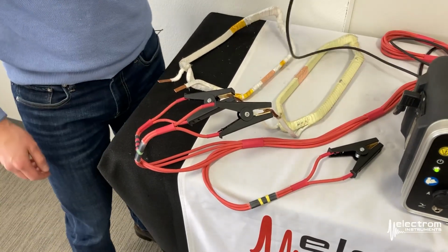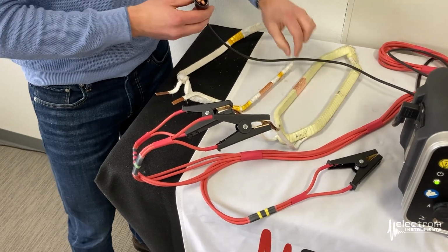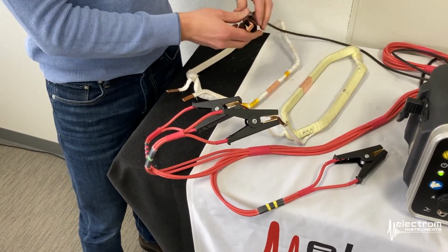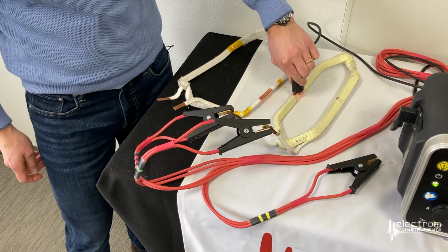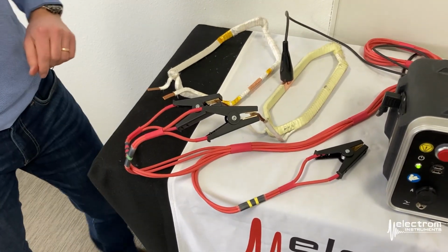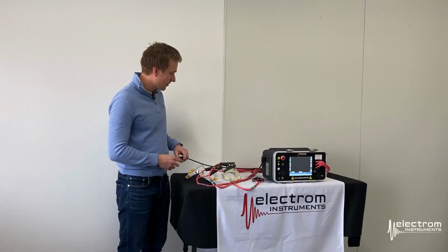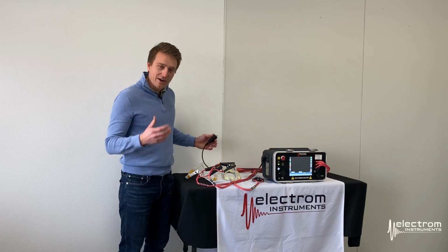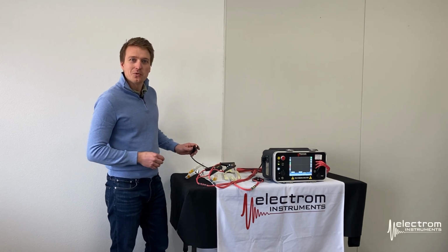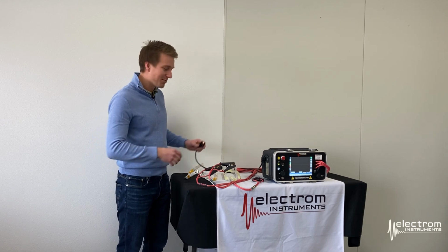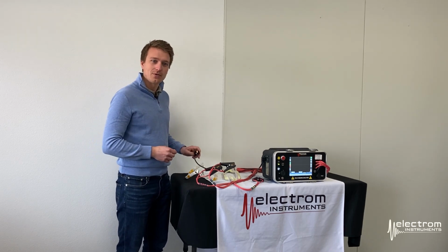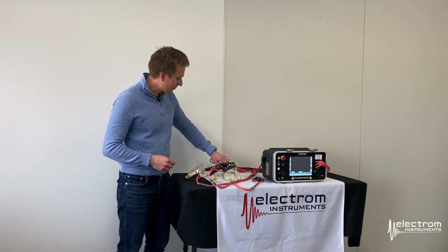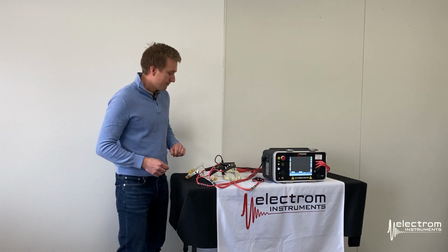And we have our ground clip. If the coils are inserted in a stator slot, then you connect the ground clip to the frame of the motor. In this case, we've just added a little copper foil to the main insulation of the coil, and we'll clamp it on here. For a brand new coil, that might not be the best way to ground the main insulation, but maybe have a cradle or another ground plane you can connect it to. So we'll do it like that.